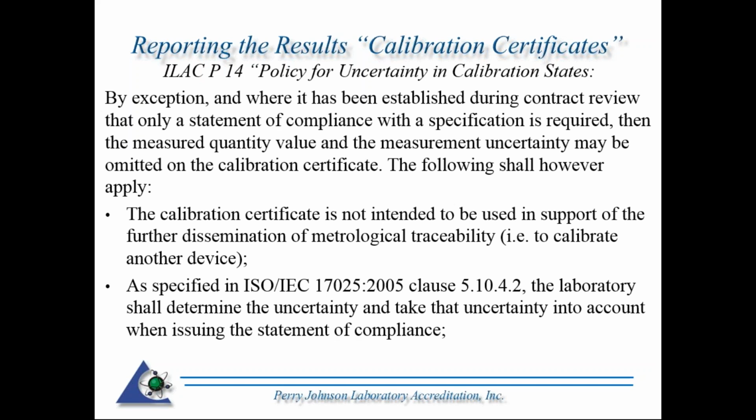Going on, as specified in 17025, clause 7.8.4.2, the laboratory shall determine the uncertainty and take the uncertainty into account when issuing the statement of compliance. I'm sorry, 7.8.4.2 is still reporting the results, but that is when you make a statement of compliance, you have to take uncertainty into account.